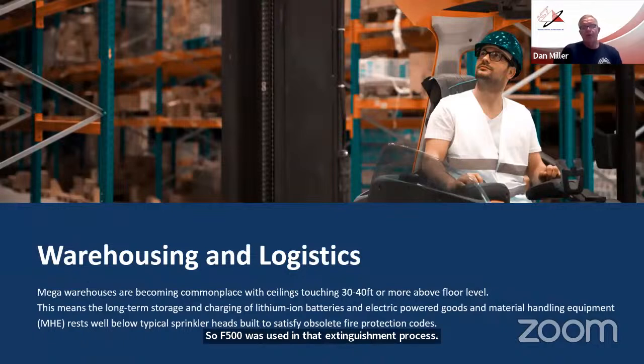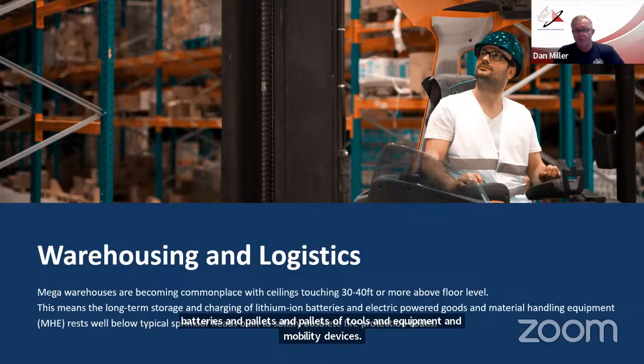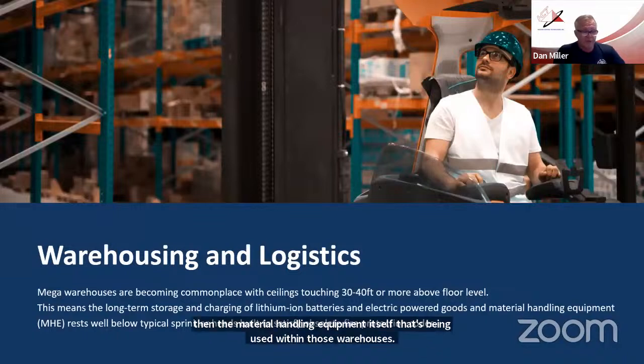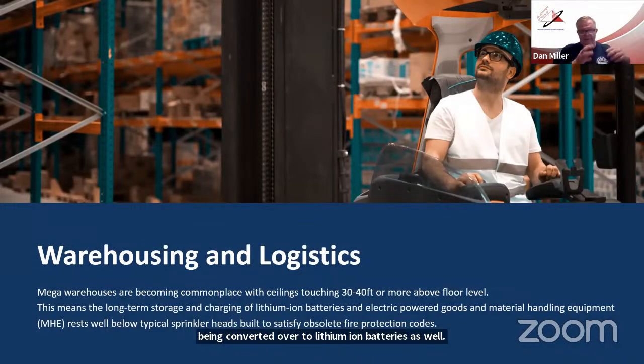Warehousing and logistics: when we think about warehouses with high rack storage, we're thinking about 30 to 40 foot high ceilings, and early suppression fast response, or ESFR, sprinkler heads that may not be up to the challenge of what's being stored on the racks nowadays, like lithium-ion batteries and pallets of tools, equipment, and mobility devices. The material handling equipment used within these warehouses is also being converted to lithium-ion batteries, so you have both the somewhat static hazard of the items on the rack, and the material handling equipment moving around the warehouse that could present a problem at any point.